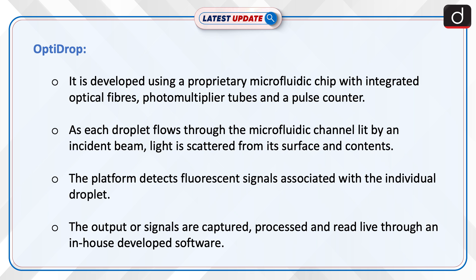OptiDrop is developed using a proprietary microfluidic chip with integrated optical fibres, photomultiplier tubes and a pulse counter. As each droplet flows through the microfluidic channel lit by an incident beam, light is scattered from its surface and contents. The platform detects fluorescent signals associated with the individual droplet. The output signals are captured, processed and read live through an in-house developed software.